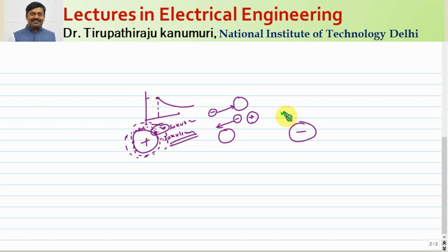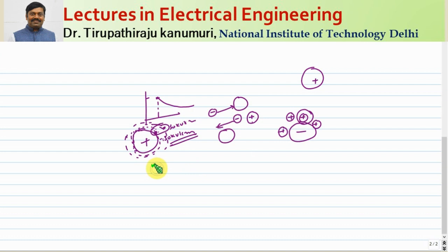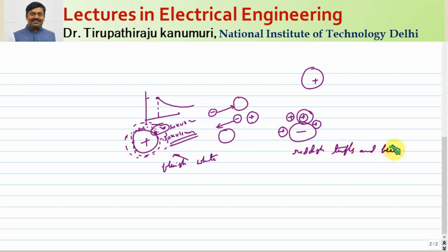For a negative conductor, only ions form at the surface. Since ions have greater weight, their mobility is lower compared to electrons. Because of this lower mobility, the color visible at the negative conductor is different. In DC conditions, a bluish-white color appears on the positive conductor, while on the negative conductor — due to lower carrier mobility — reddish tufts and beads are formed.